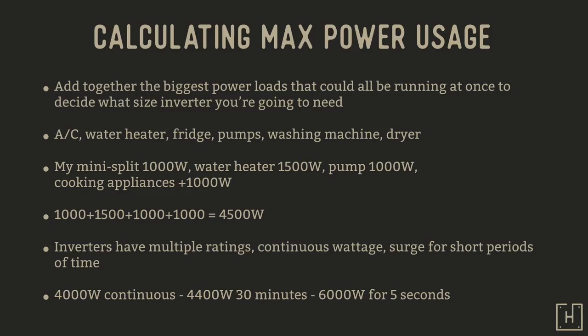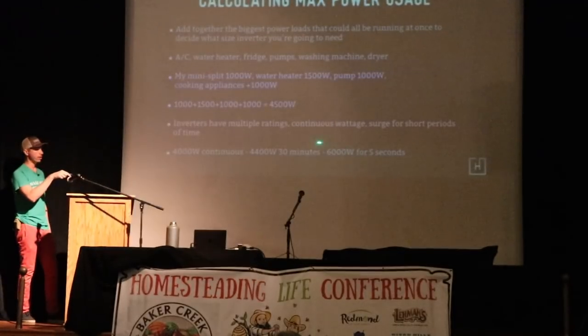I know that if everything is running at once, I need to be able to supply my house with 4,500 watts. One cool thing about inverters is that they have multiple ratings: a continuous wattage, and they can also surge for certain periods. My inverter is a Schneider SW4048. It can run at 4,000 watts continuous, 4,400 watts for 30 minutes, and it can surge up to 6,000 watts for about 5 seconds, mainly for pumps and motors that require a very quick surge of power.